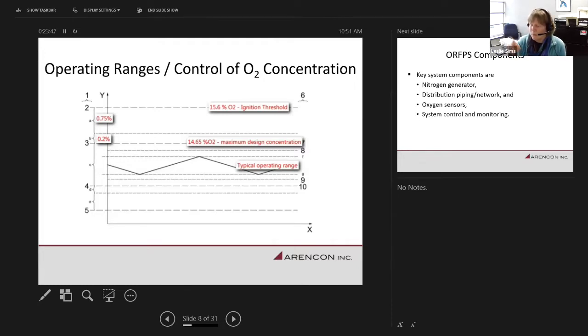So you'll see there's some bounce up and down. You'd set the level, say at time 0, and then you push nitrogen into the space. As you build up more nitrogen, you hit a lower oxygen level, and the system says, okay, that's enough for this space. So you hit your first low level set point, and it basically says, turn the nitrogen off for a little bit. We've got it, we're fine.